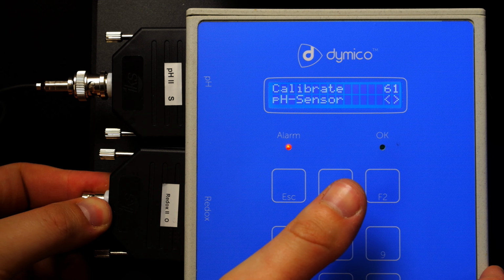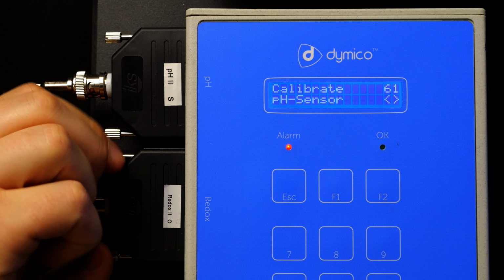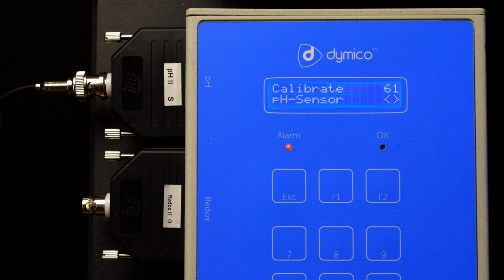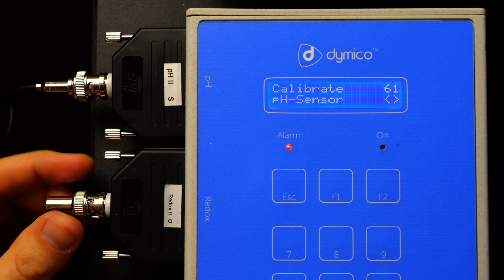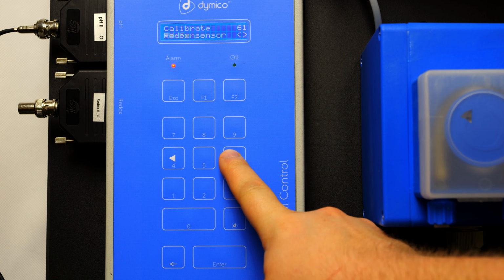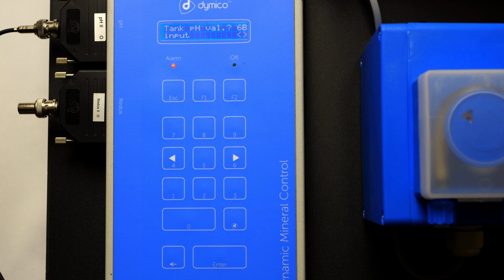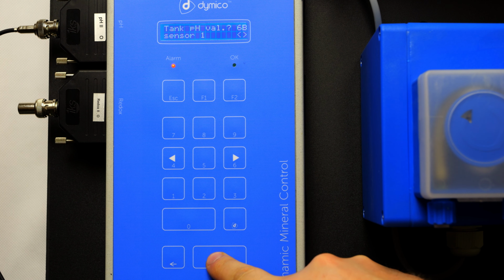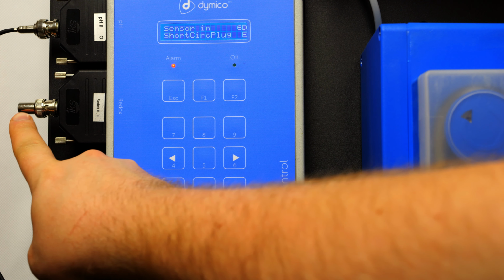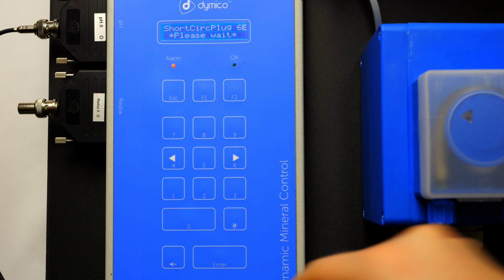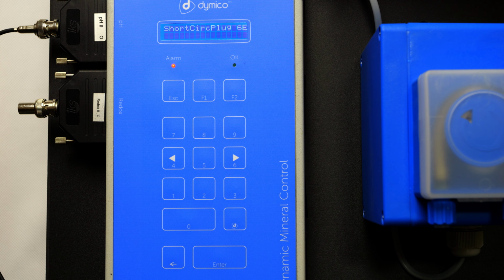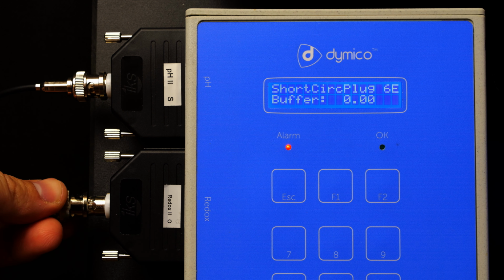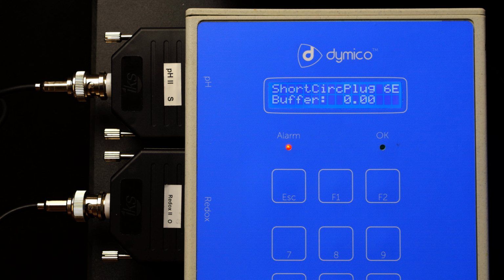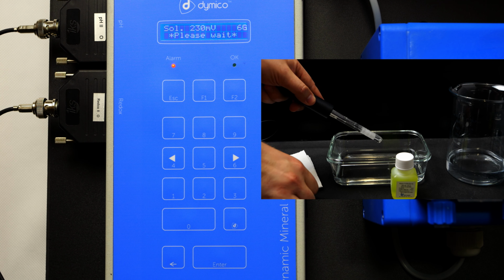Once the pH probe is calibrated, connect the redox module to the sensor 2 socket of the Aquastar. Connect the metal cap for the first point of the calibration. Navigate to main menu, calibrate, redox sensor, press enter. To correct redox measurement according to pH value, select sensor 1 as input for tank pH value setting. After the first calibration point, remove the metal cap from the redox black module and connect the redox probe. Clean it and use 230 mV standard solution for the second calibration point.